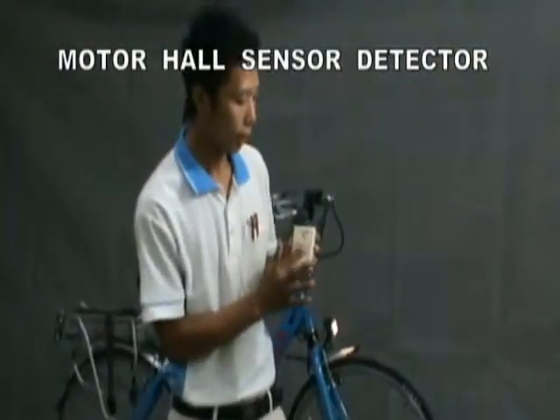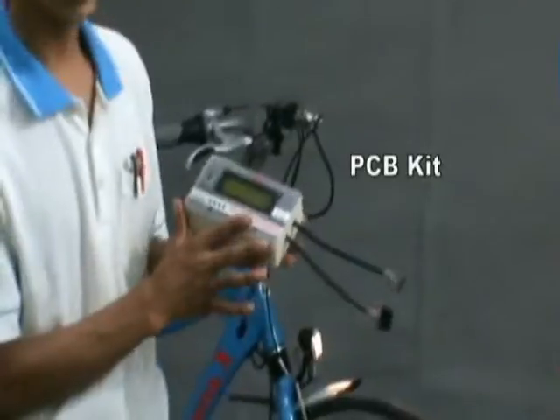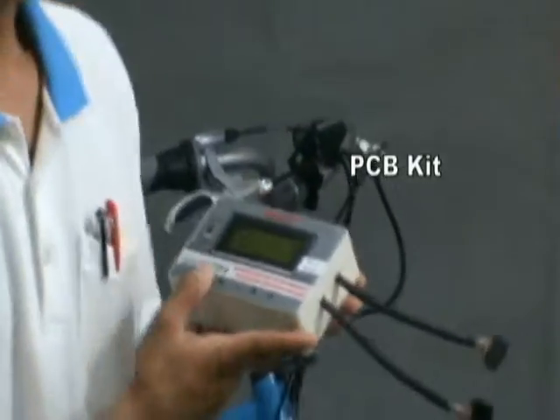When the error code 1 appears on the display, we have devices to check. This one is our motor hall sensor detector to check the motor. And this one is our PCB kit to check the hall sensor.